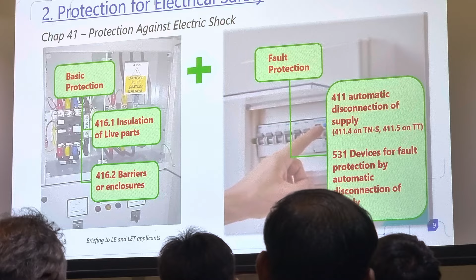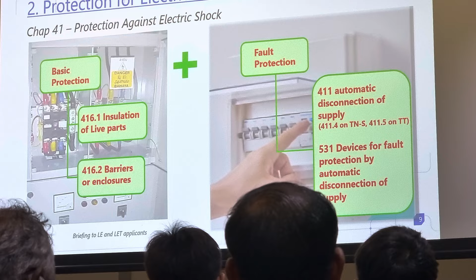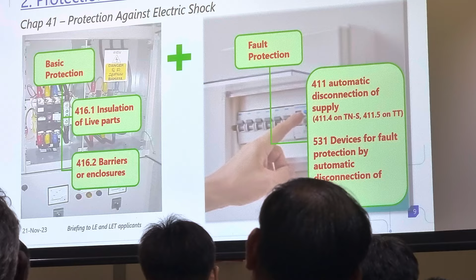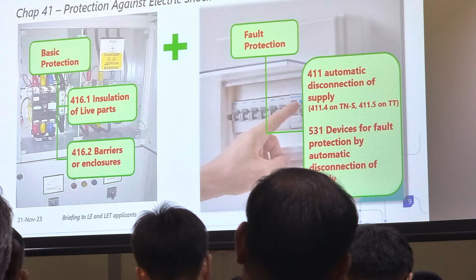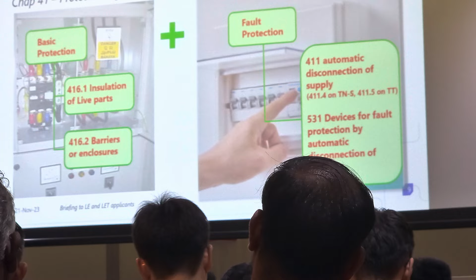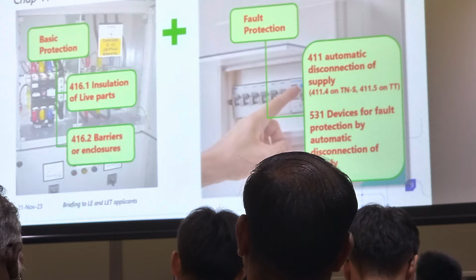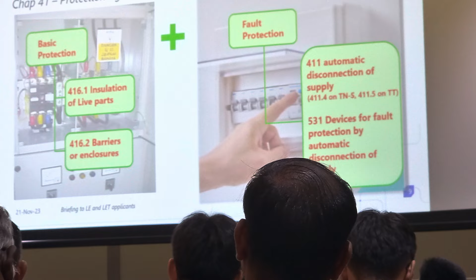Under the code, there are three important requirements. Number one, we must have protective earthing. The next thing is to be earthed properly. Later on, I'll elaborate more about earthing. Earthing is important to make sure that the fault will be cleared in the shortest possible time. Next, bonding. Extraneous conductive parts and exposed conductive parts must be bonded. This is to ensure that the touch voltage is minimized as low as possible. So to fulfill the two requirements I talked about, the duration and the magnitude, we want earthing and bonding to work together to ensure that the duration and the magnitude are as low as possible.